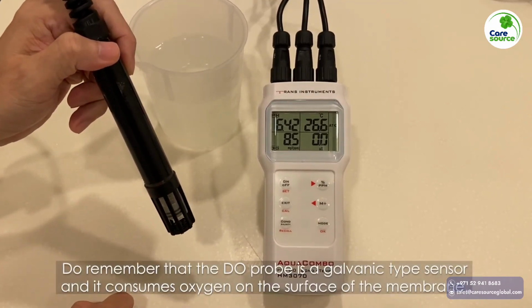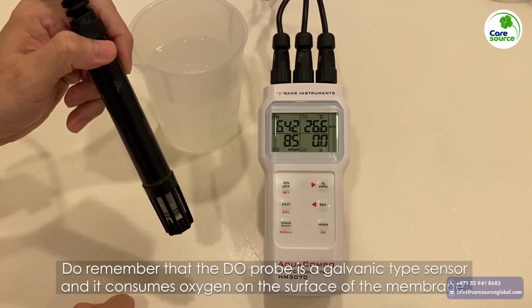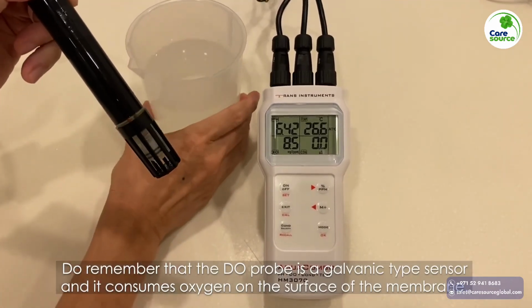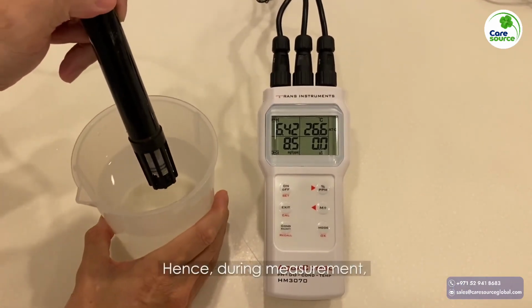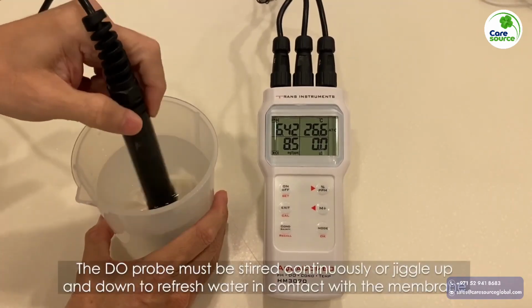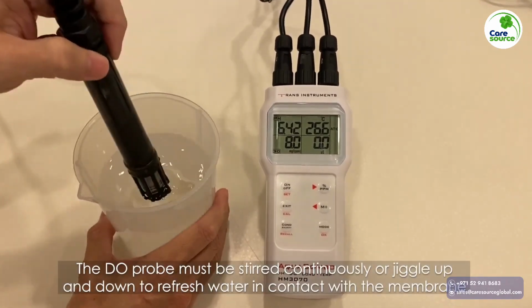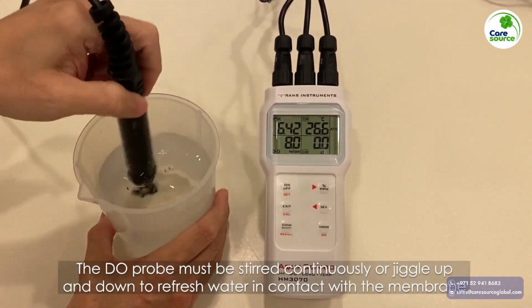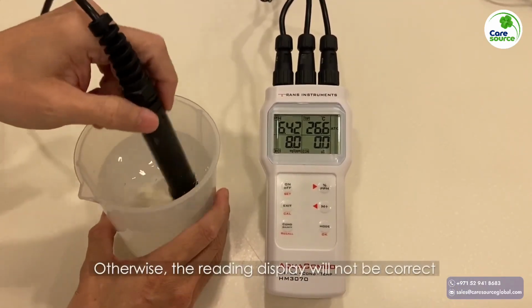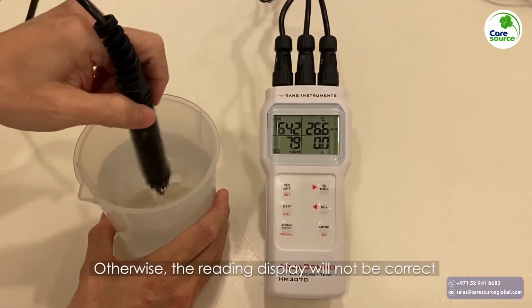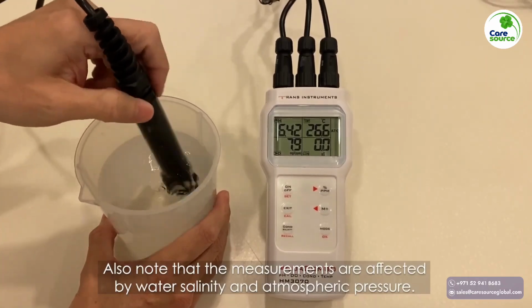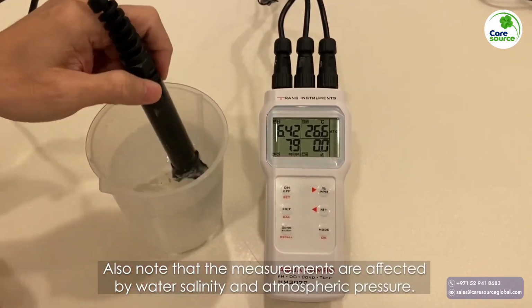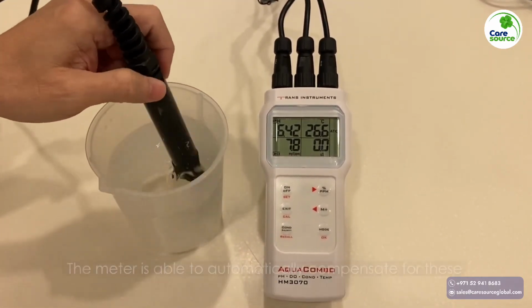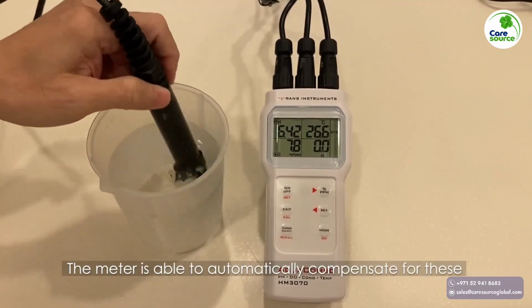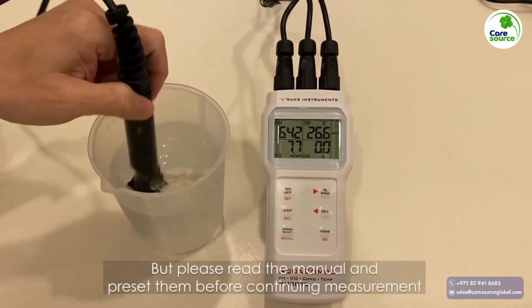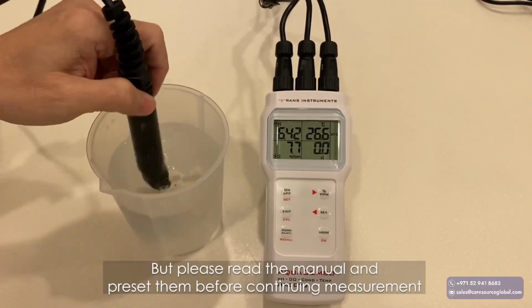Do remember that the DO probe is a galvanic type sensor and it consumes oxygen on the surface of the membrane. Hence, during measurement, the DO probe must be stirred continuously or jiggled up and down to refresh water in contact with the membrane. Otherwise, the reading display will not be correct. Also, do note that the measurements are affected by water salinity and atmospheric pressure. The meter is able to automatically compensate for this, but please read the manual and preset them before continuing measurement.